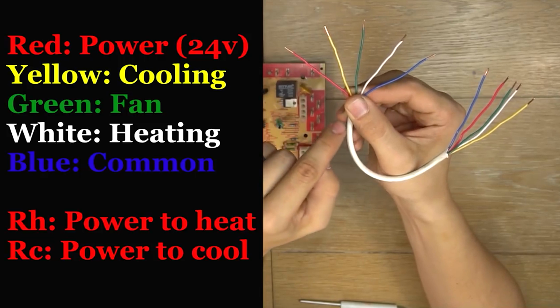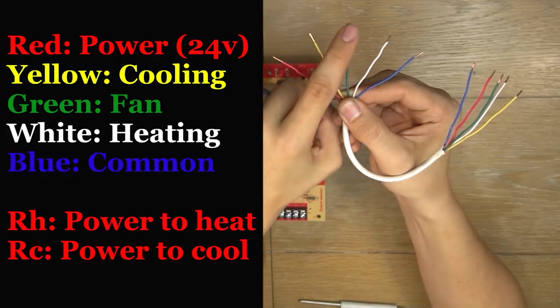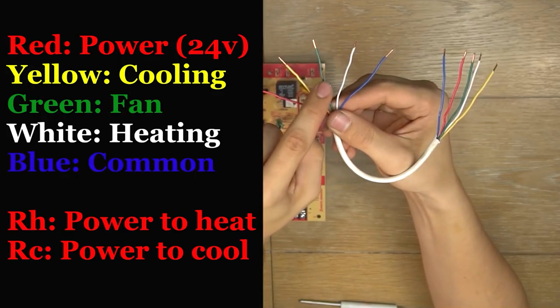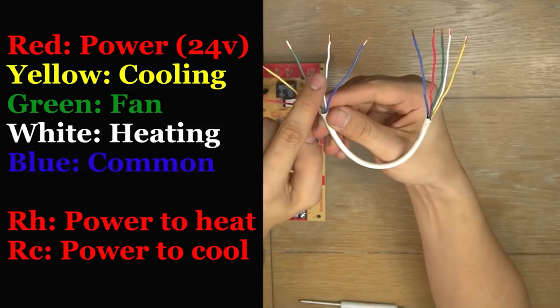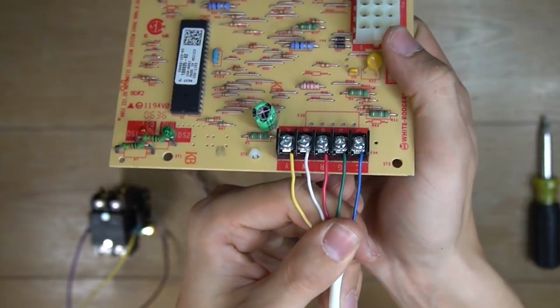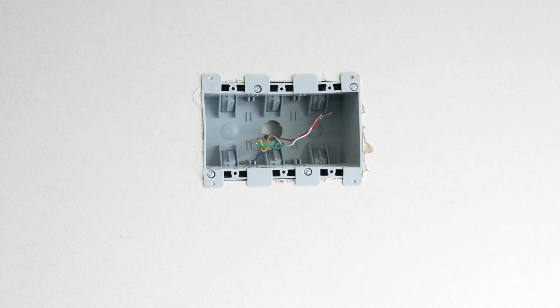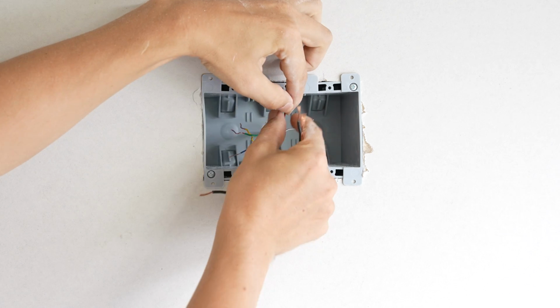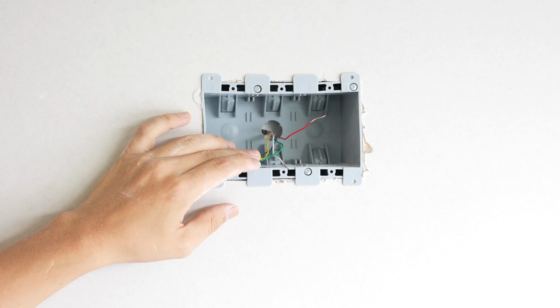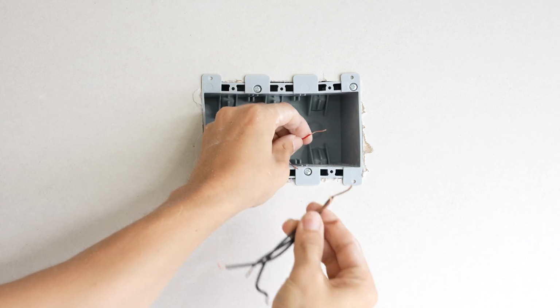Before I continue, if anyone needs a reminder, here's the standard color code for a basic thermostat. I have a whole separate video on this if you need more information. Basically, what's going on here is that I'm going to need power to go to all 3 of these switches. So what I'm going to do is add 3 pieces of wire to R, the red wire, which is the power wire.